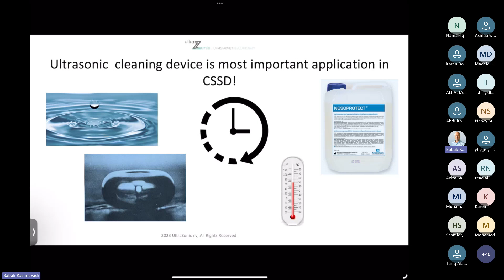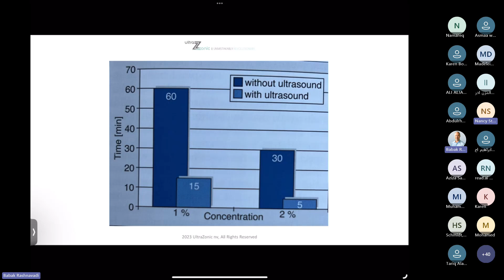Now here, this is something smart to check and to show you. When you just have a sink and you use 1% concentration of detergent, you will need 60 minutes to achieve the same results as when you put 1% in your ultrasonic device, where it only takes 15 minutes of cleaning. Now, if you put more additives, more detergent in percentage, then you will minimize the time in your manual sink, but also the time in your ultrasonic device. So that means the concentration of chemistry is still very important. You cannot clean your instrument in an ultrasound as long as you're not using a decent detergent or a decent disinfectant. Next, please.